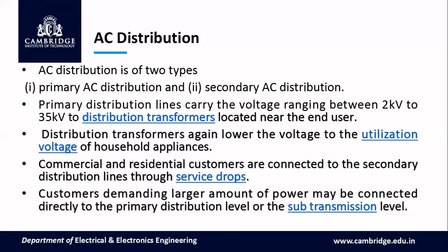So that will again be stepped down. Commercial and residential consumers are connected to the secondary distribution lines through the service drops. Customers demanding a larger amount of power may be connected directly to the primary distribution level or the sub-transmission level. Some industries require 2 kilovolt or 1.1 kilovolt directly, and in such cases they can be connected directly to the primary distribution lines.